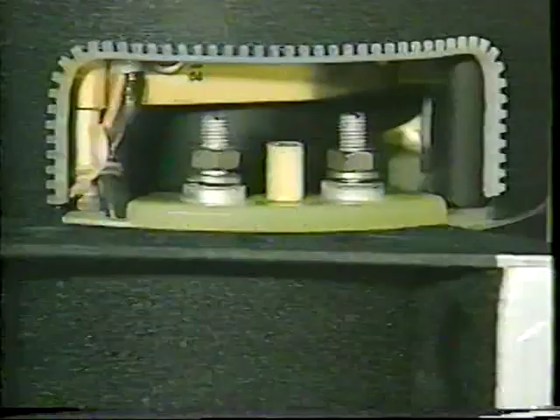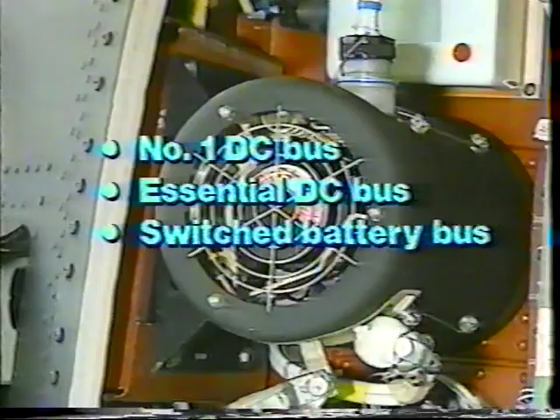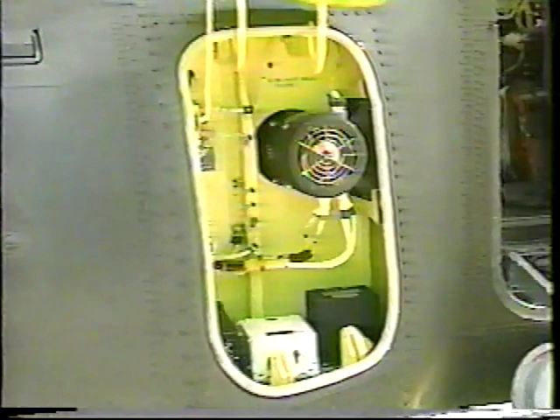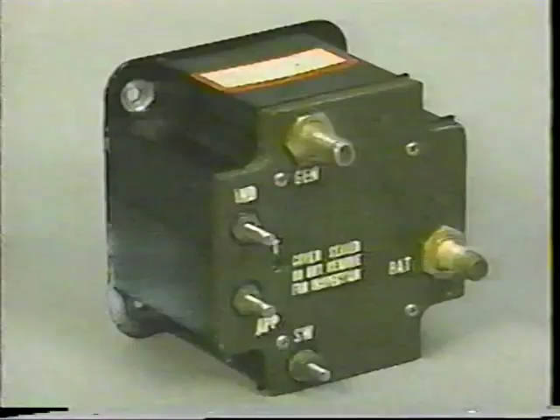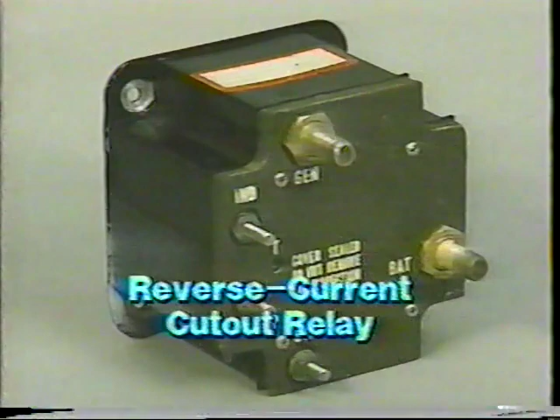An AC quick disconnect input connector is located on top of the TRU with positive and negative output terminals located underneath. The number 1 TRU, located in the left electrical compartment, powers the number 1 DC bus, the essential DC bus, and the switched battery bus. The number 2 TRU, located in the right electrical compartment, powers the number 2 DC bus and the essential DC bus. To protect and control the TRUs, reverse current cutout relays are connected to the TRUs.